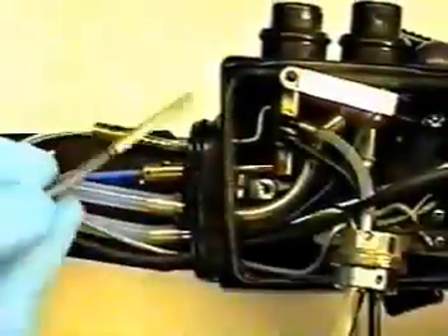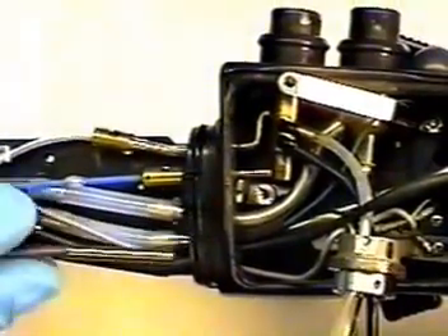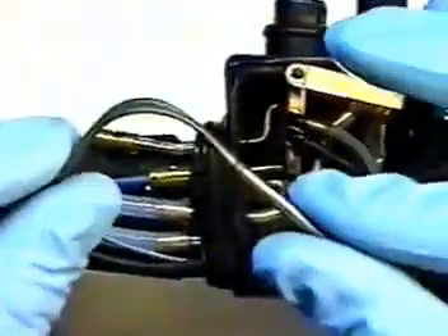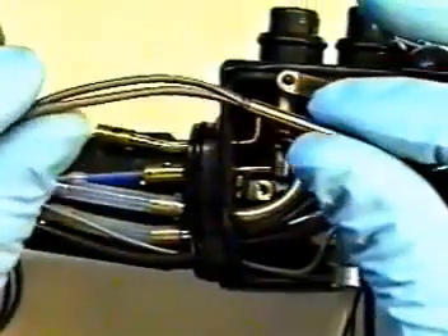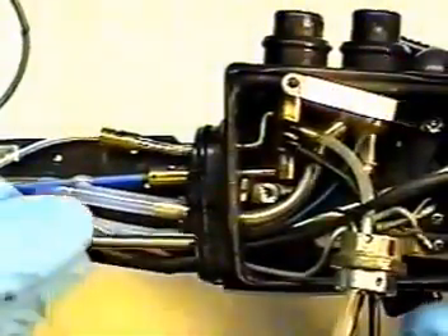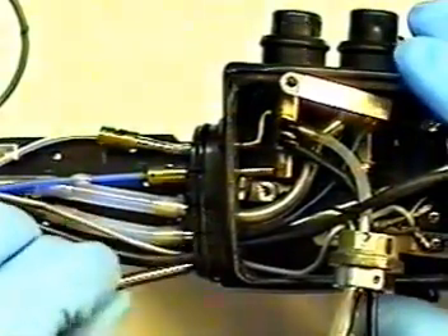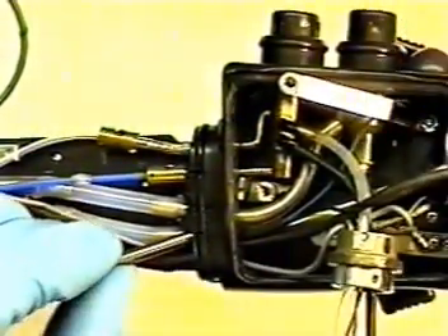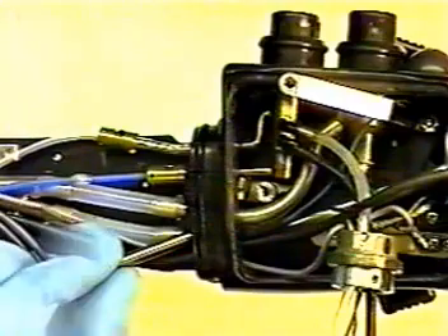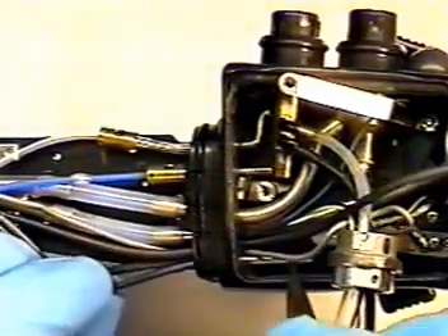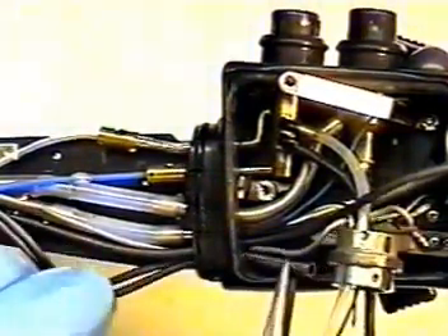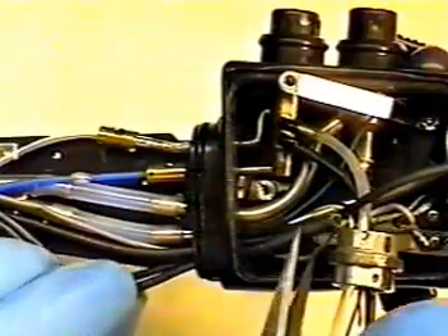Pull remainder of illumination light bundle through body section, being extremely careful not to kink or bend or crush light guide itself. Use a pair of tweezers if necessary, and only grip on the metal shaft and not the illumination bundle itself.